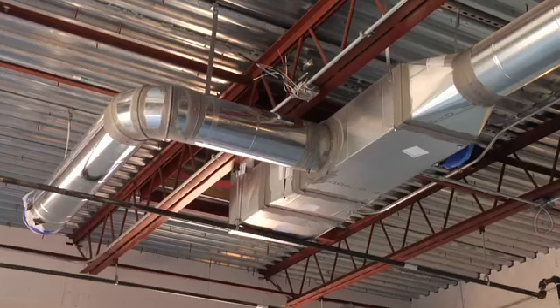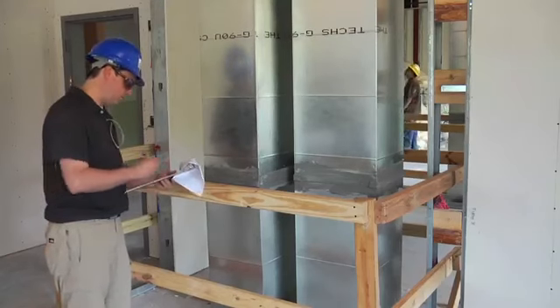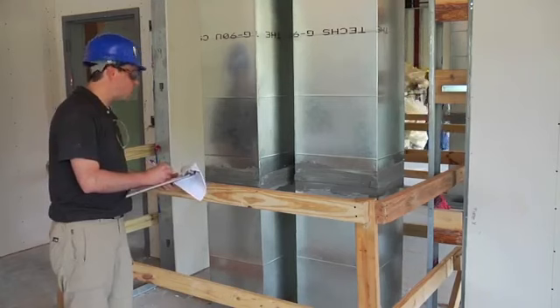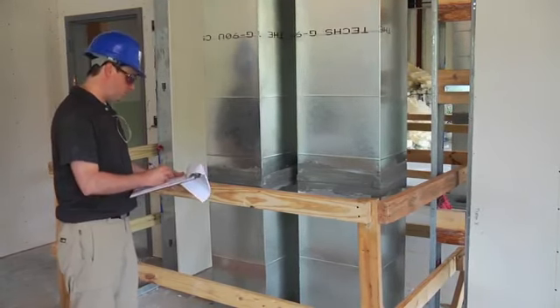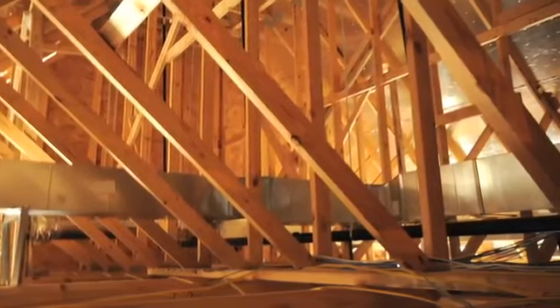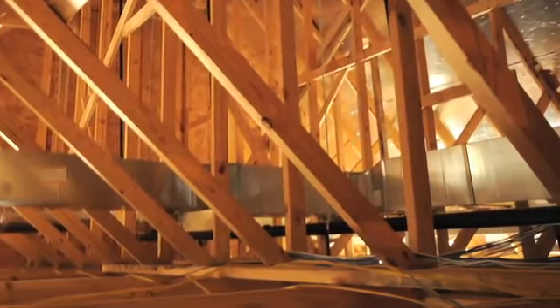There are multiple mandatory requirements that must be verified as well, such as Requirement 12, duct sealing. Verify that pressure-sensitive tape used as the primary sealant is certified to comply with UL 181A or UL 181B, and verify sealing of longitudinal and transverse seams for ducts in unconditioned spaces.